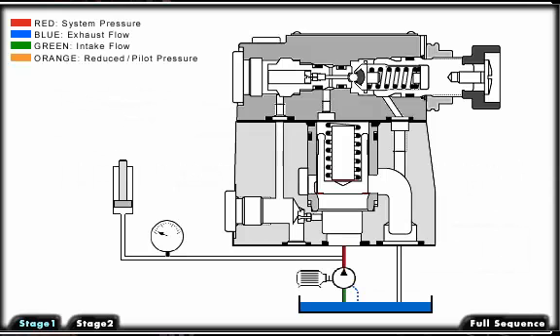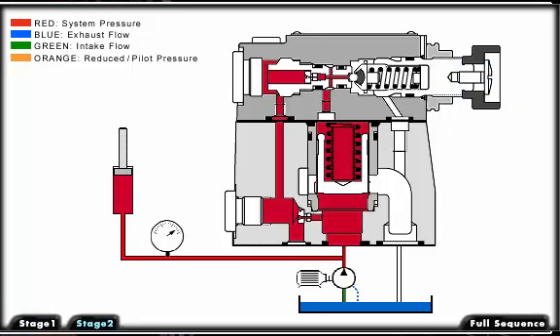The pilot operated pressure relief valve comprises a valve body, a main spool cartridge, and a pilot valve with a pressure setting adjustment. The pressure present in the primary port acts on the bottom of the main spool, and at the same time the pressure is fed to the spring-loaded side of the main spool via the control lines and damping orifices. The pressure is also present at the ball of the pilot valve.